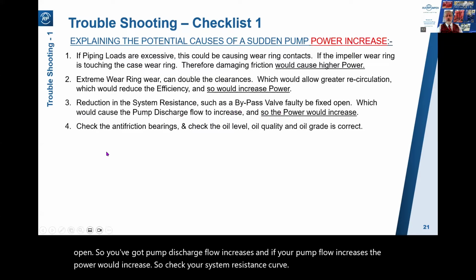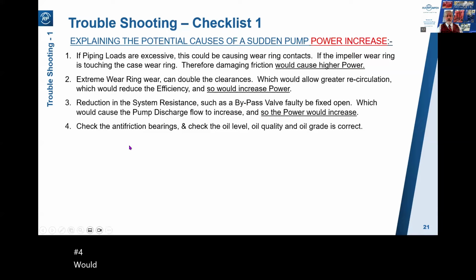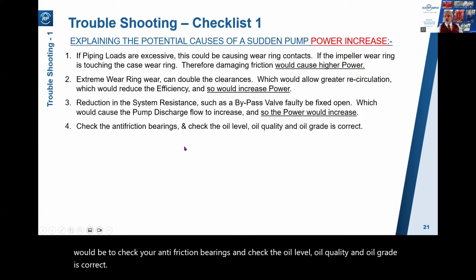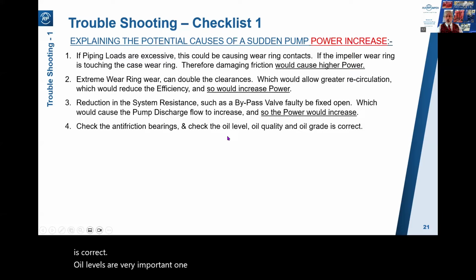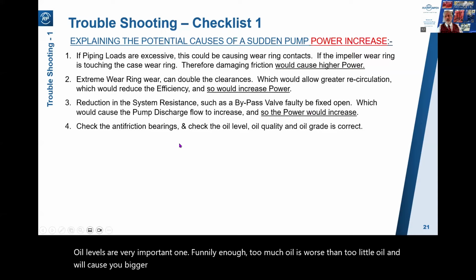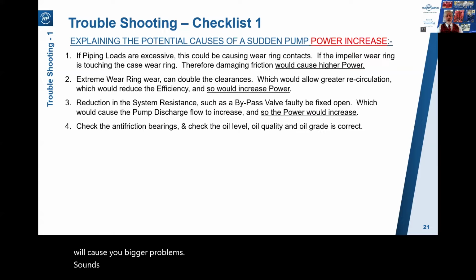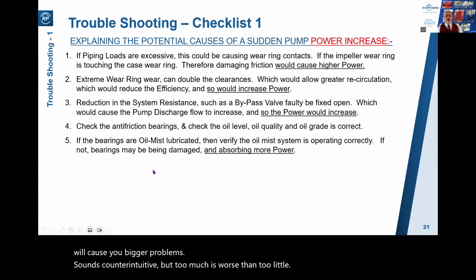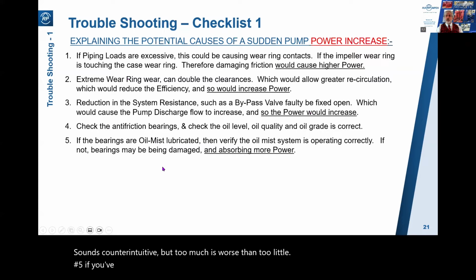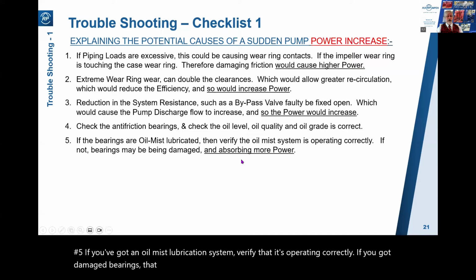Number 4 would be to check your anti-friction bearings and check the oil level, oil quality, and oil grade is correct. Oil level's a very important one. Funnily enough, too much oil is worse than too little oil and will cause you bigger problems. Sounds counterintuitive, but too much is worse than too little. Number 5, if you've got an oil mist lubrication system, verify that it's operating correctly. If you've got damaged bearings, that would lead to high power.